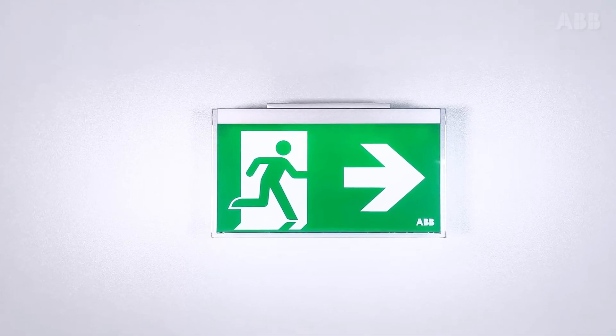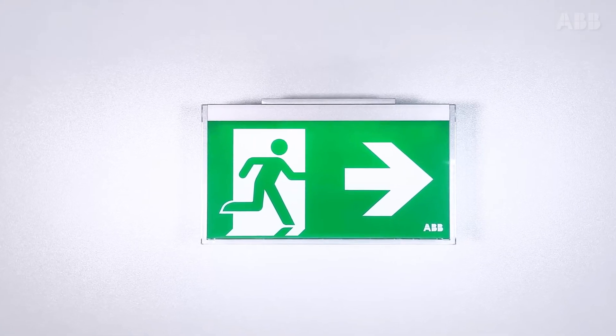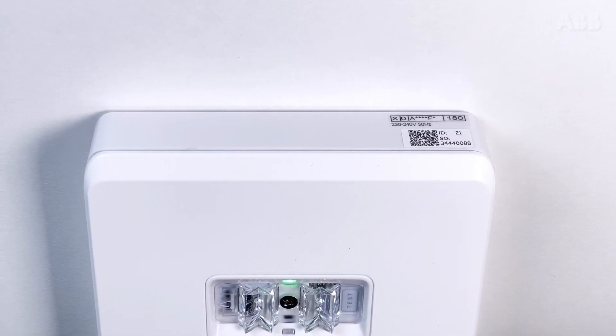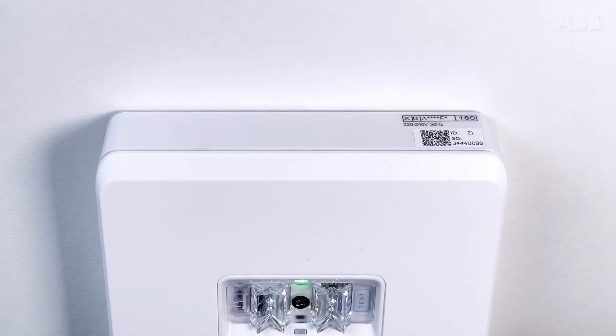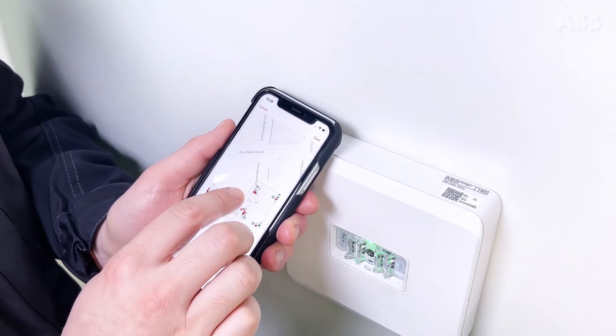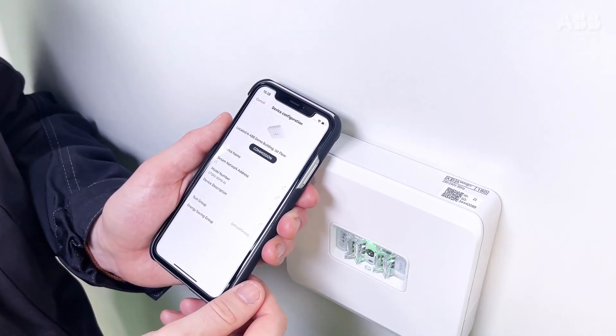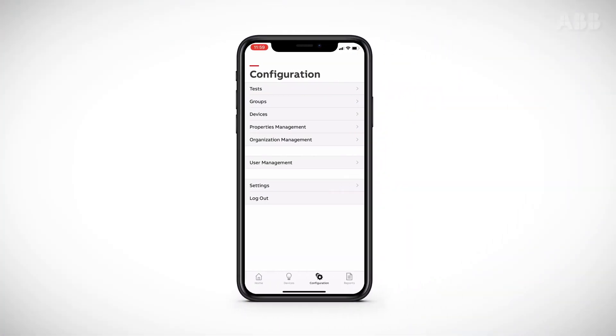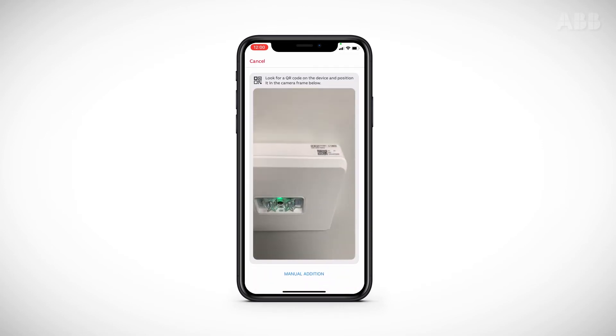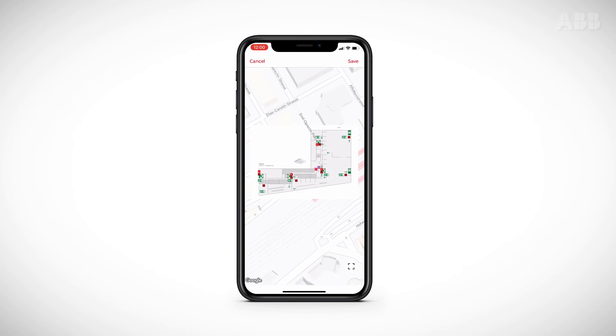When you order an addressable ABB Luminaire, you will receive a luminaire configured with a single address and equipped with QR codes — one on the luminaire and the other on the packaging. A luminaire can be commissioned directly using the QR code without the luminaire being connected to a power source or the bus cable. It is possible to position the luminaire on the map and complete the description fields. However, the luminaires will only be able to communicate with the Navio Pro gateway when they are powered and connected to the bus cable.